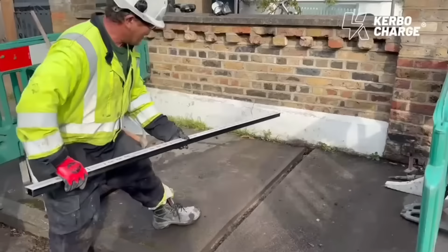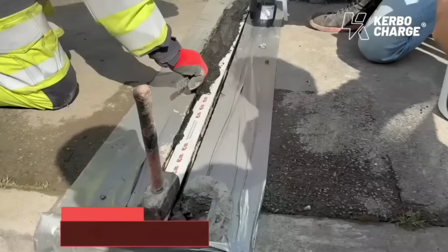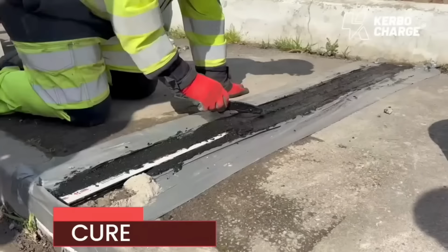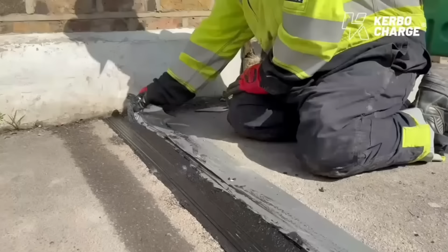The author of the Wiring Regs, the IET, has stepped in as cross-pavement EV charging begins to roll out across the UK. As more councils approve pavement cable gullies for EV charging, electricians are being warned that these installs are about much more than avoiding a trip hazard. A new IET advisory says the biggest danger could be electric shock. It says your first job is to check the situation with your local authority. Most installs need highway approval, and you'll need to know who owns the pavement before you reach for the disc cutter and start hacking into it like a meringue.